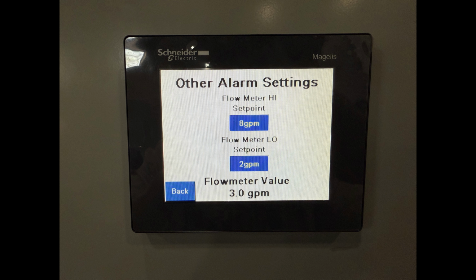Now if we move on to the other alarm settings, we can see the flow meter high set point and flow meter low set point, and also the flow meter value. We're at 8 gallons per minute for the high and 2 gallons per minute for the low, just because we want to keep that in between those 2 points. But if you ever wanted to keep higher than that, you'd go in here. Just make sure that you don't trip any other alarms.